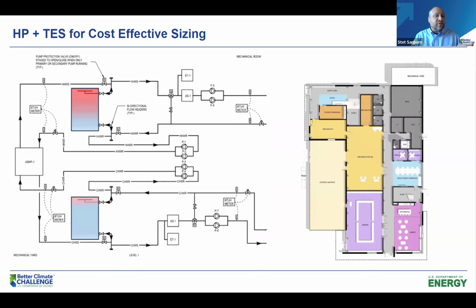If you're challenged still with footprint, instead of hot water or cold water storage, consider phase change materials. There's a number of manufacturers out there that are doing both hot storage and chilled storage with phase change. And that can reduce the footprint by upwards of 60%. So again, a number of technologies out there can get you a tailored solution that will operate more efficiently.